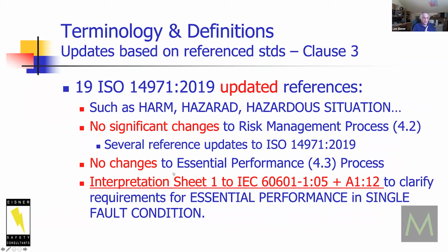This is where I thought Luke's presentation and my comments about 601 line up really well. So essential performance is the clinical function of your device and basically the limits in single fault and normal condition. And it's not all your clinical functions. I highly recommend not saying it's all your clinical functions. It's one or two. Keep it simple. Otherwise, you're going to test forever and it's going to be a nightmare. Keep it as simple as possible, but do the most critical ones. There were no changes to essential performance.